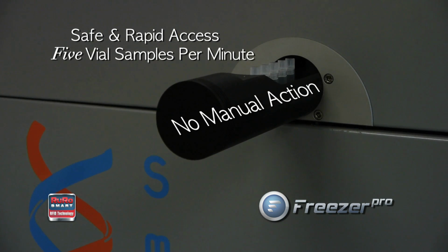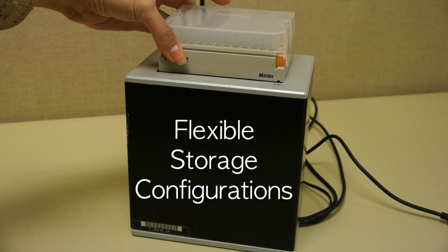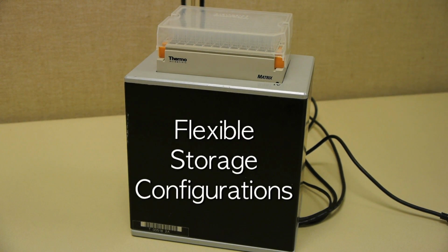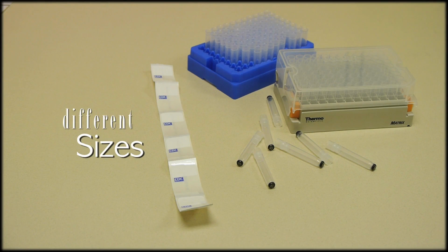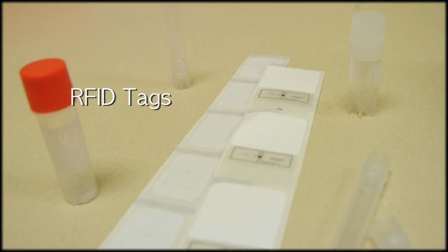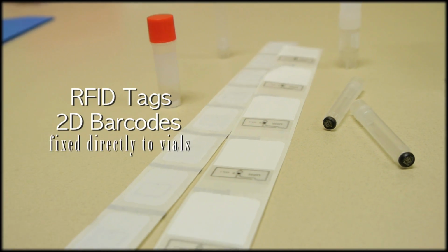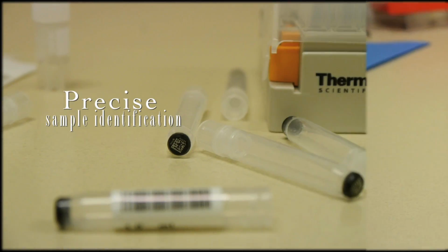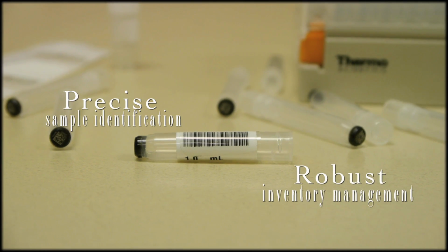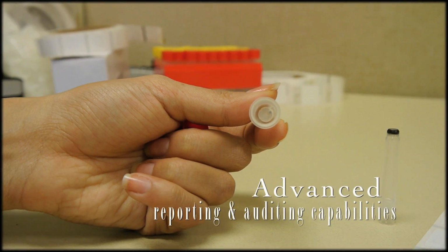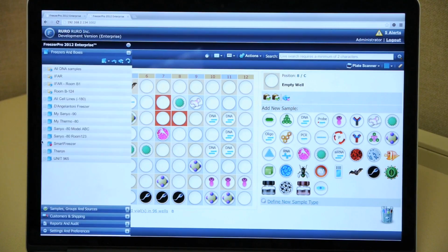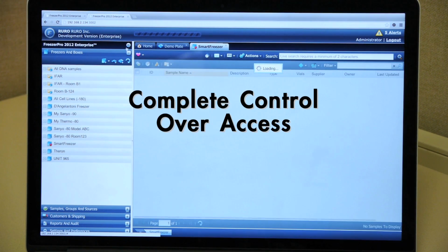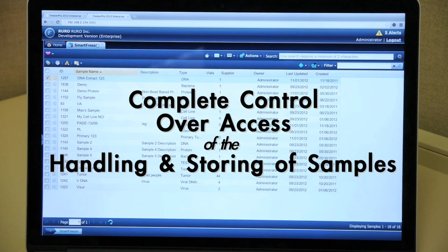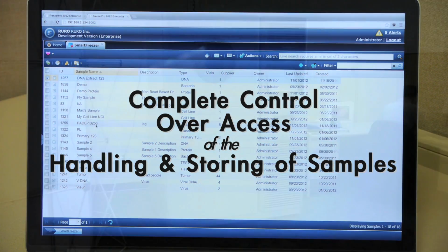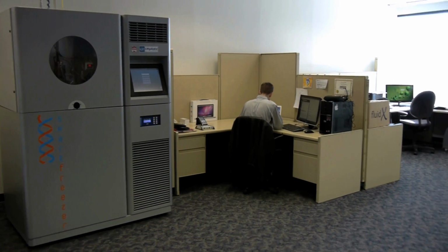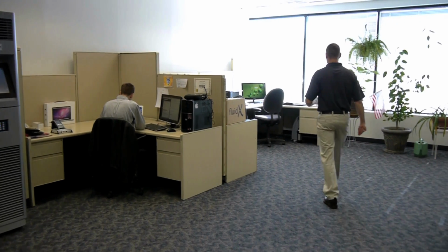of any manual action. SmartFreezer offers flexible storage configurations with the ability to store sample vials of different sizes, types, and shapes. RFID tags and 2D barcodes affixed directly to vials provide precise sample identification and robust inventory management with advanced reporting and auditing capabilities. The FreezerPro software allows for complete control over access for handling and storage of samples according to established authorization levels. The quiet operation of SmartFreezer allows it to be placed in almost any location.